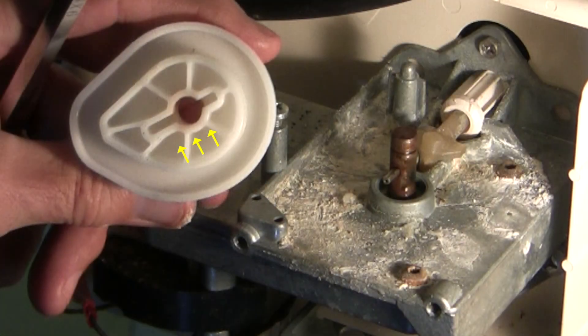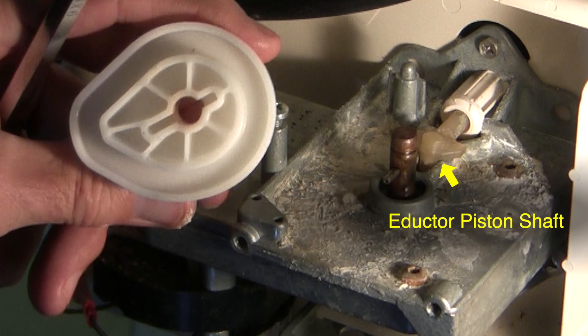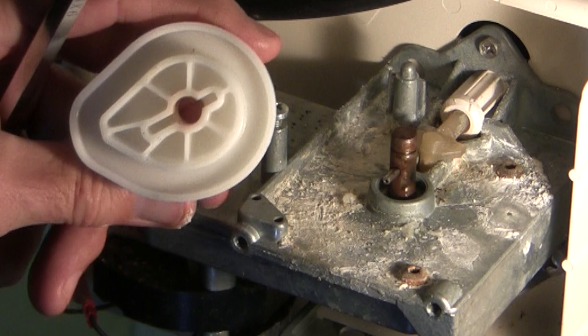I didn't get a good shot of this when it went back on, so I'll show you now. Under the cam there's an offset diagonal slot, shown with yellow arrows, into which an offset roll pin on the shaft, shown with a red arrow, needs to mate up. Behind this is the eductor piston shaft with a raised bump, shown with a yellow arrow, that needs to ride inside a groove on the under surface of the cam, shown with a green arrow. When you reinstall, it's possible to accidentally rotate that eductor piston shaft upside down, so you need to be sure the raised bump on the piston shaft mates properly with the under surface of the cam.